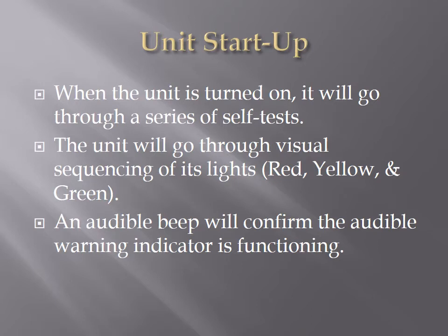So when you start the unit up, it'll go through a series of self-tests, and all this is normal for any monitor that we use. The unit's going to go through a visual sequence of its lights. It may go from red to yellow to green, and that is all normal. You're also going to hear an audible beep that's going to confirm that the audible signal and the indicator are functioning, and all this is normal. And the reason that we want both audio and visual in a monitor is that we may be in an environment that's, for example, loud, whether it be some external noise or talking amongst company members, things like that. And we might miss that audible beep, but we can certainly see the light indicators. Again, the red, the yellow, and the green. That will help us determine if we're going from a safe environment into a more toxic or dangerous environment.